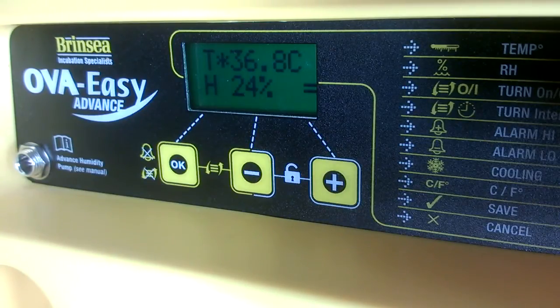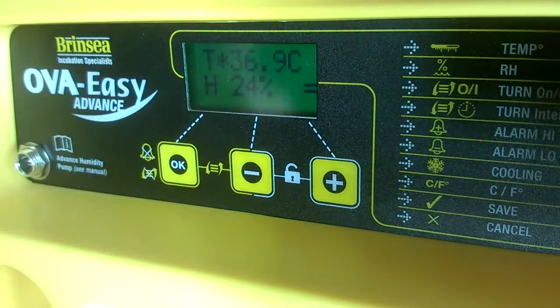and then to go back and check it again against the thermometer, because we may still be a few points out, in which case we need to go into the calibration menu again and adjust it again, save it, and then check it again half an hour later. And we have to continue that process until we are confident that the temperature that we read on our thermometer and the temperature that we have here, once it's stabilized on this menu, are the same.